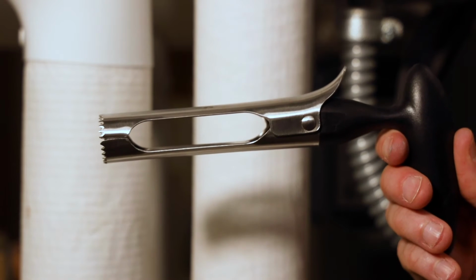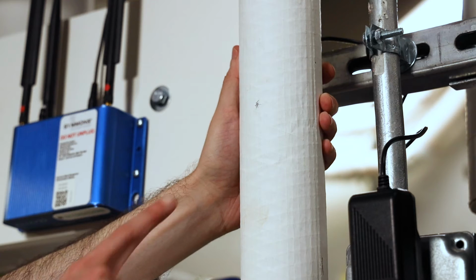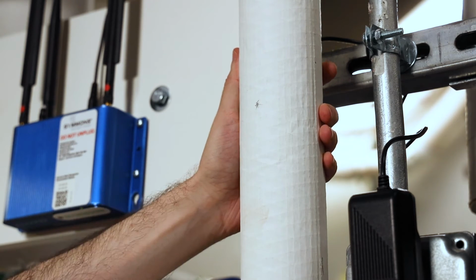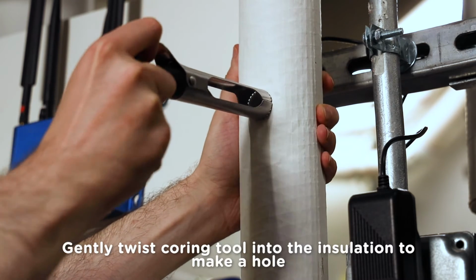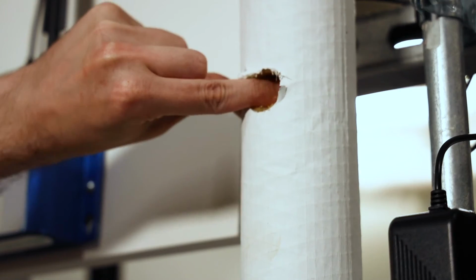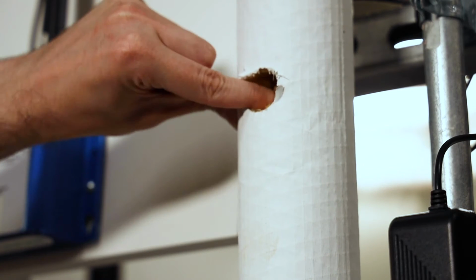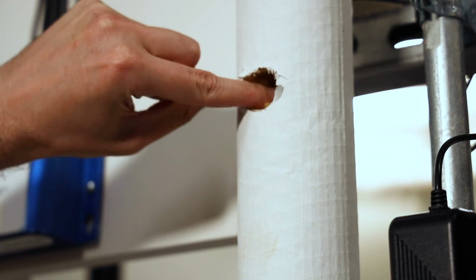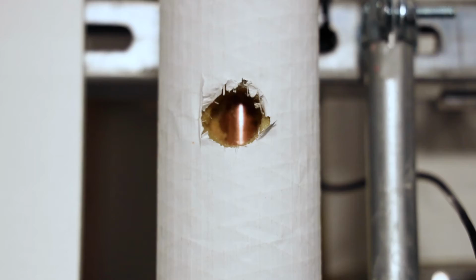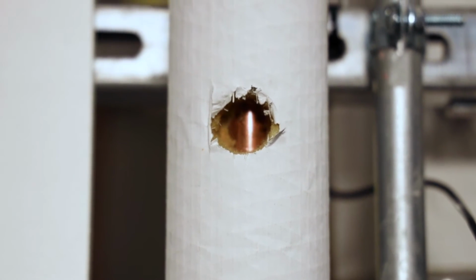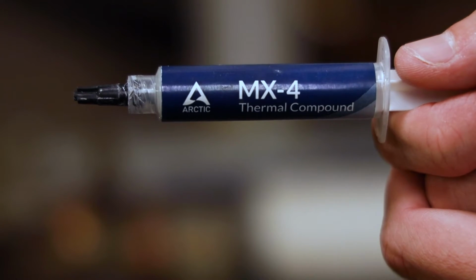For this step, we'll use the coring tool to cut a nice round hole in the insulation for the sensor probe. Just find a good spot on a section of straight piping and gently twist the coring tool into the insulation to make a hole. When you're done, just make sure there's no insulation blocking the hole. Stick your finger in and tuck any remaining insulation out of the way so you have a nice clear view of the pipe inside. The Evolution kit also includes a tube of thermal paste.